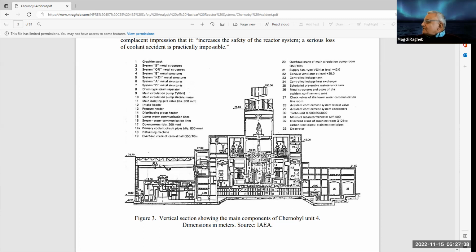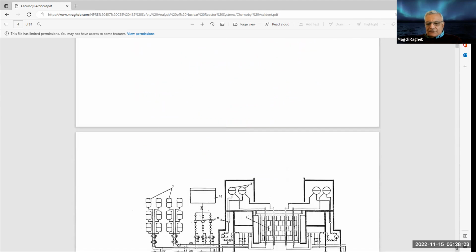And we devoted a whole chapter to what happened in the SL-1 reactor, the military reactor in the United States. If you have metal interacting with water, you get a chemical reaction that can be extremely violent in that case. So I surmise that the core melted and interacted with the water under the core. A steam explosion took that lid, which I have shown you in the earlier diagram, and threw it up in the air. Now, the graphite was seeing the air, heat was being generated from the fuel, the graphite caught fire, and they had basically a very serious situation where radioactivity was released from the reactor itself.